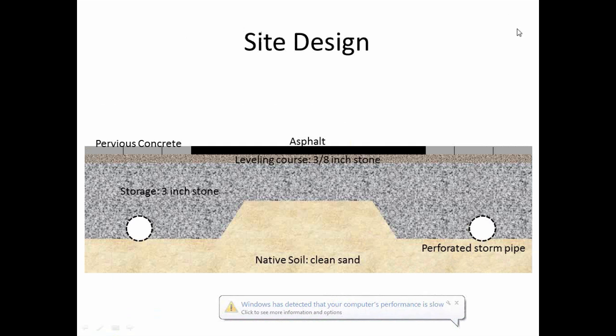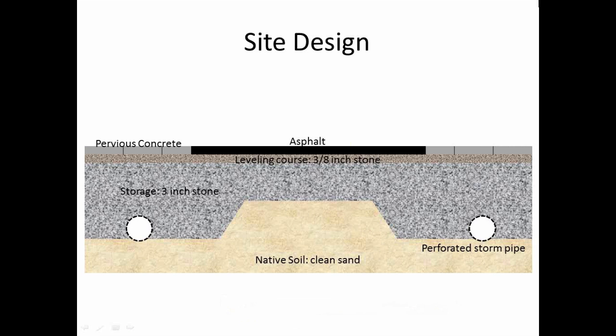No, that's good. Okay, so the perforated storm drains then go to a discharge point, and in the discharge, we had them construct a concrete wall that is in the middle of the concrete box. The water will come out of the pipe into the box, and then it has to rise to a certain level. In that concrete wall, we placed a weir and a pressure transducer, so we would be able to measure the water level on the system side of the wall. If high enough, it will go over the weir and begin to discharge down the hill. So we would have a measurement of that water height, and we would be able to tell when water would be leaving the system.